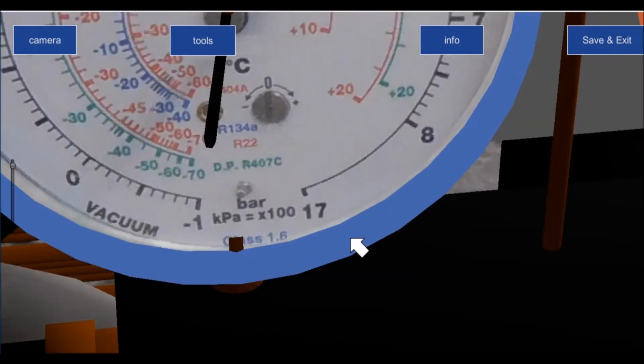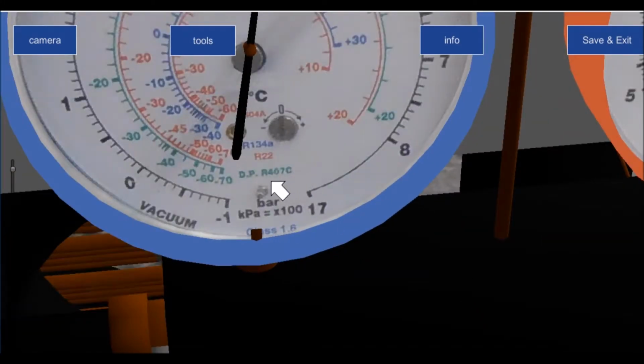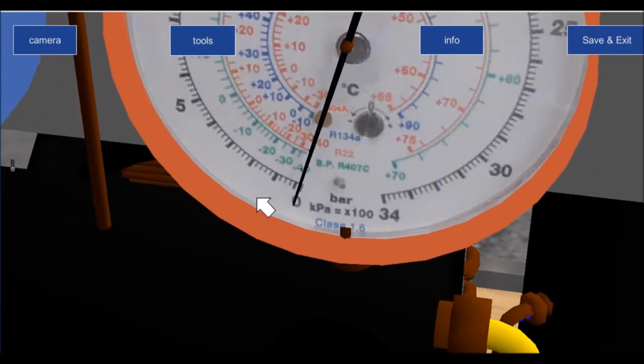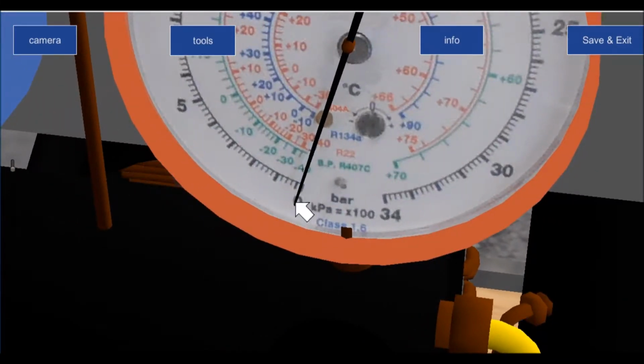As soon as I have no pressure on the gauge line, the first thing I do is I check and make sure. So if I go over to this one, which is at 0, the first thing I do is check and make sure that this needle is lined up with the 0. And how I do that is I actually adjust this screw minus or plus just to get that lined up here. So that's something I can do myself, and something I do every time before I put the gauges on.